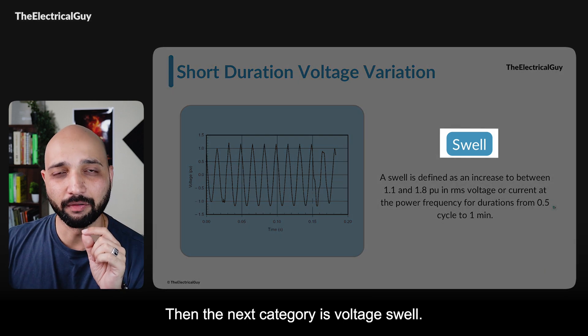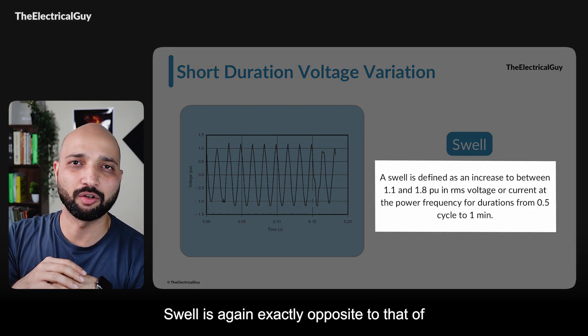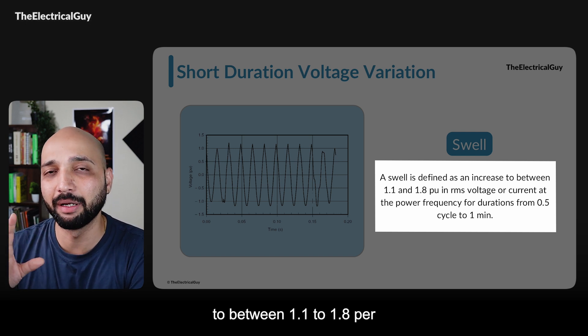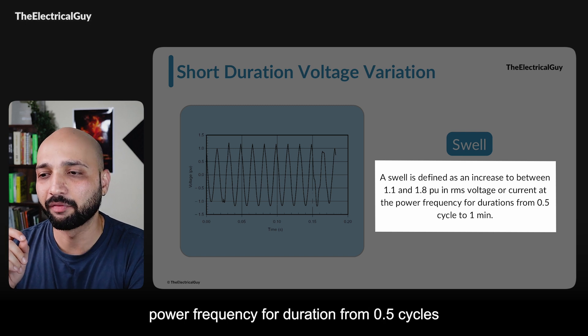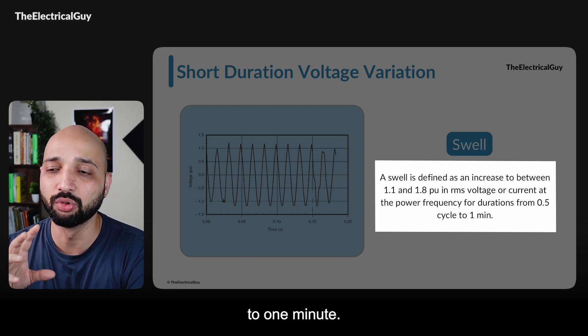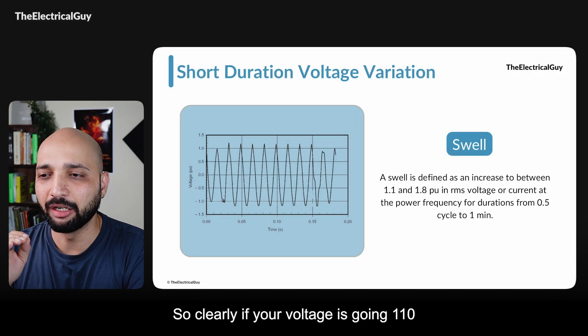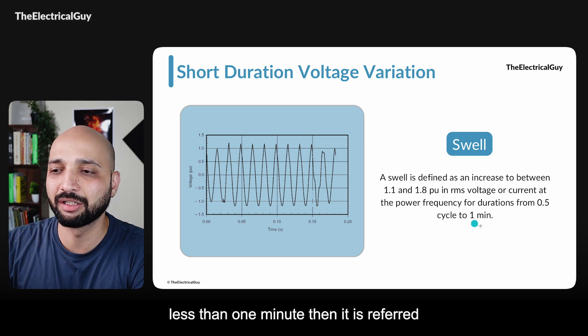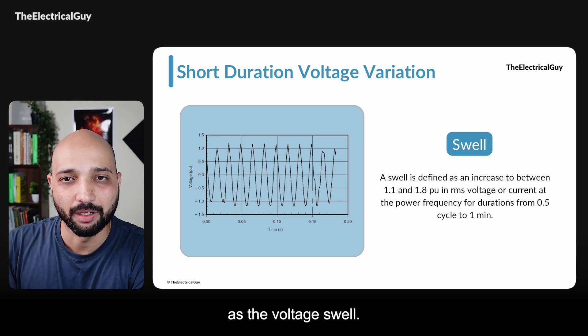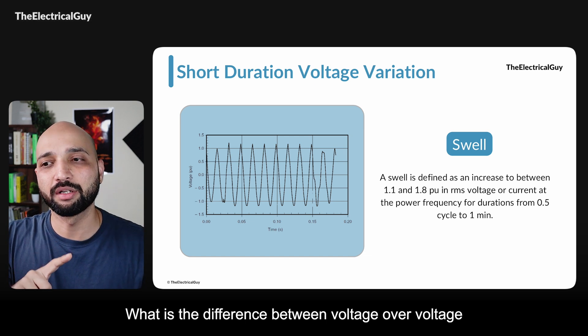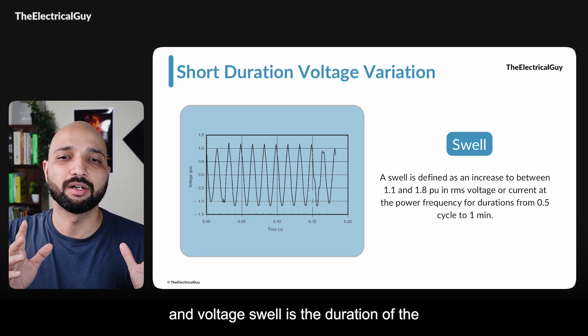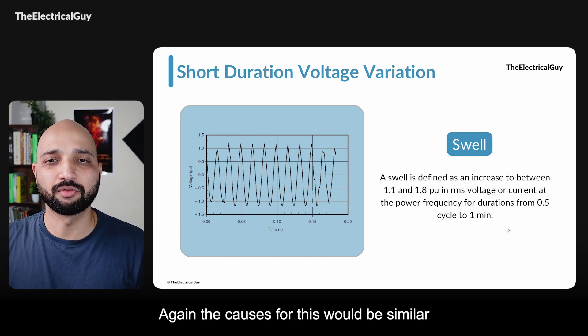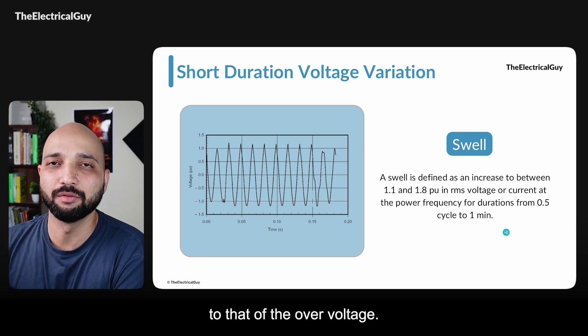The next category is voltage swell, exactly opposite to voltage sag. A swell is defined as an increase to between 1.1 and 1.8 per unit in RMS voltage or current at power frequency for a duration from 0.5 cycles to one minute. If your voltage goes 110 to 180 percent for a duration less than one minute, it is referred to as voltage swell. The difference between over voltage and voltage swell is the duration the voltage remains in the system — swell is there for less than one minute. Causes are similar to those of over voltage.